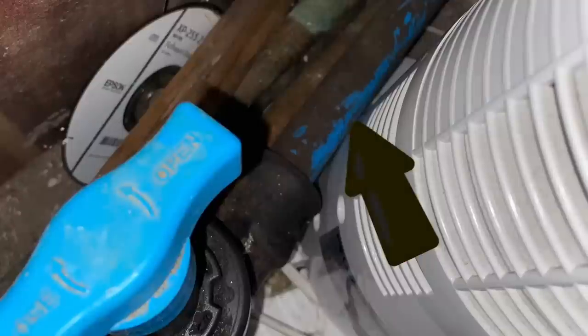What actually turned out to be the case — as you can see on camera — is that there's a massive insulated section of pipework coming into the property. So it doesn't actually require the bonding. The bonding conductor can just be disconnected. That's one that as you go through the learning process — the Guilds and EAL expect you to bond the shortest piece of pipe on every end point assessment. But you never take into consideration plastic incoming services. When you go out in the real world, every new property you come into is generally plastic. Bonding isn't required.